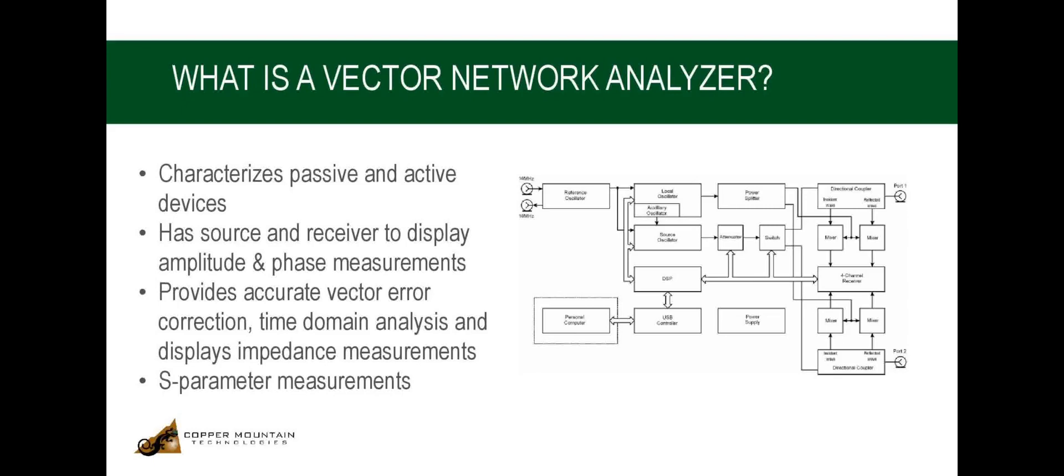The incident and the reflected waves in the directional couplers are passed into the mixers where they are converted to first IF and then passed to the four-channel receiver for further analysis. The four-channel receiver, after filtering, digitally encodes the signal and then supplies it to the signal processor.